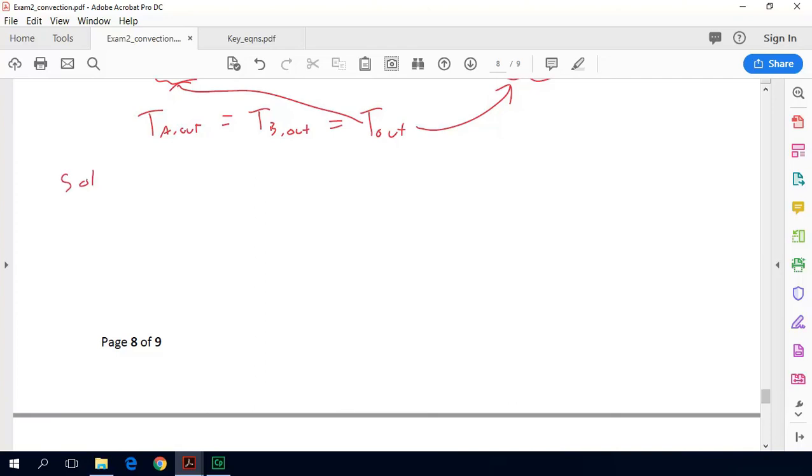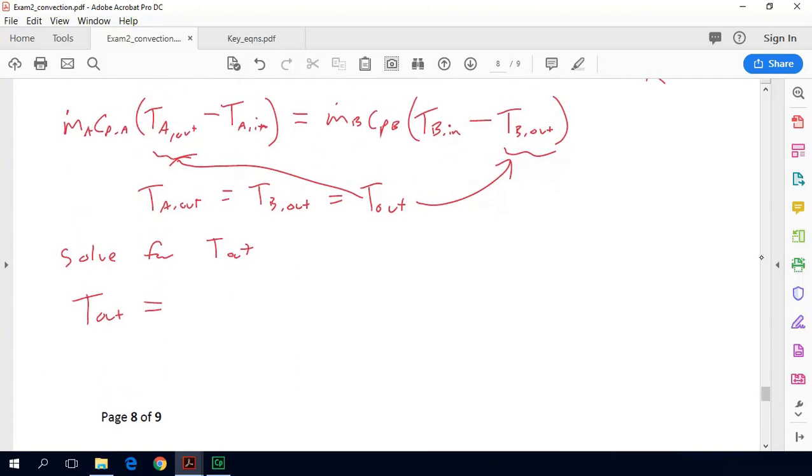So we can solve for T out. So T out is equal to, and I'm just going to do this, I'm going to skip some algebraic steps here. T out is equal to M dot A times CP A multiplied by T A in plus M dot B times CP B multiplied by T B in, divided by M dot A times CP A plus M dot B times CP B. So pretty easy, and that gives us our outlet temperature T out, which is also equal to T A out, which is what the problem was initially asking for. That comes out to be 175.6 degrees Celsius.